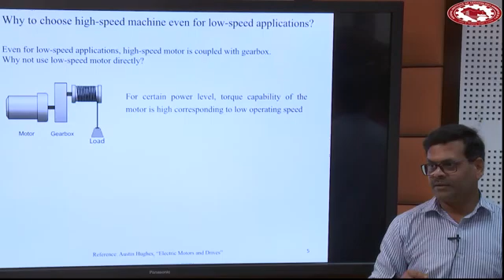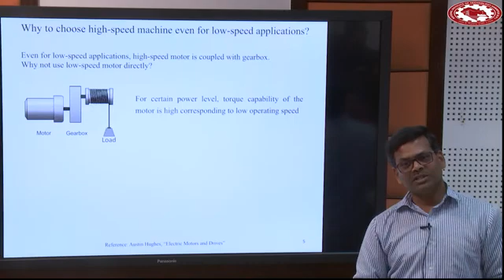So therefore the slot volume should be high. So eventually the machine size is going to be big, right? If you go for 1500 RPM, for the same amount of power, 20 kilowatt, the torque will be less, and for the same 1 Tesla flux density, the current will be less, so the size of the machine will come down. So one important advantage of going for a high speed system is that the size of the machine will be less.